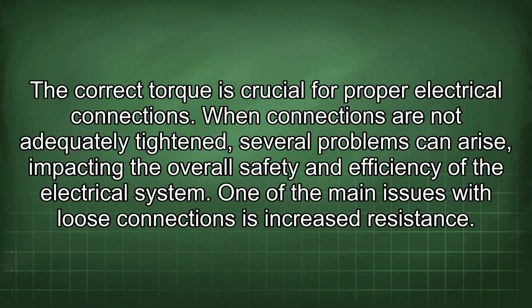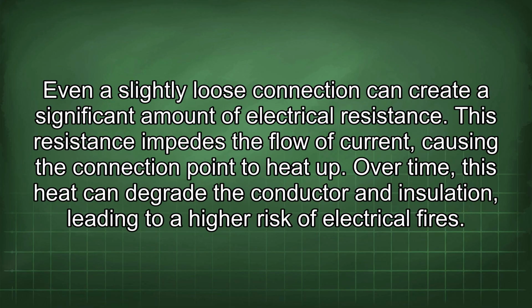The correct torque is crucial for proper electrical connections. When connections are not adequately tightened, several problems can arise, impacting the overall safety and efficiency of the electrical system. One of the main issues with loose connections is increased resistance. Even a slightly loose connection can create a significant amount of electrical resistance. This resistance impedes the flow of current, causing the connection point to heat up. Over time, this heat can degrade the conductor and insulation, leading to a higher risk of electrical fires.